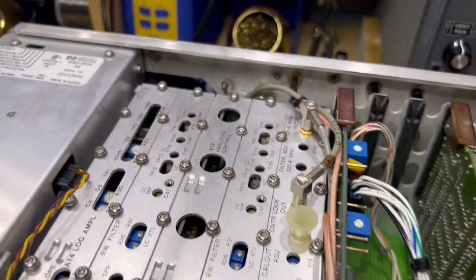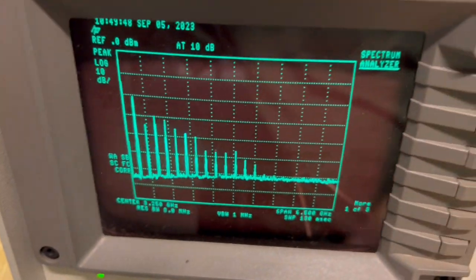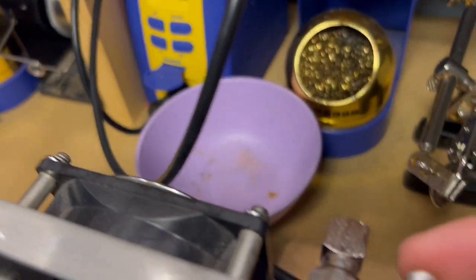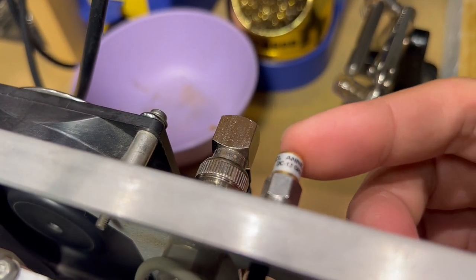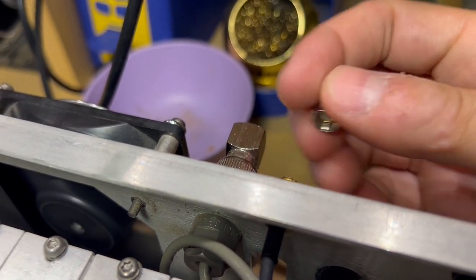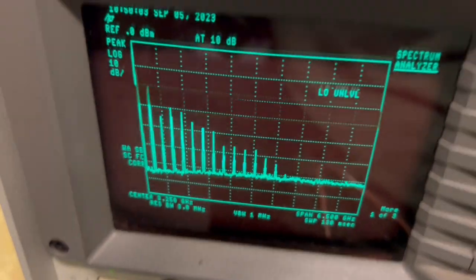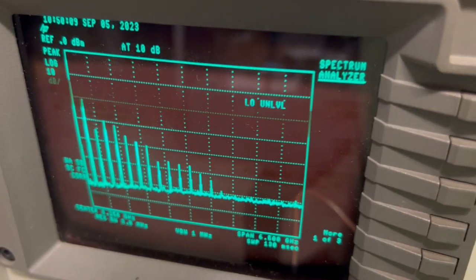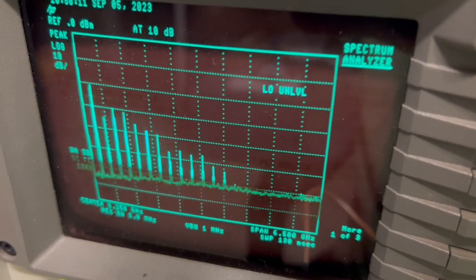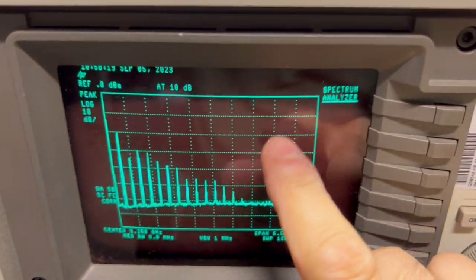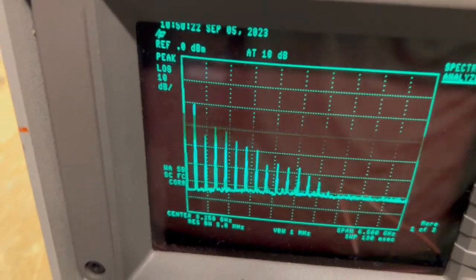Important: on the back panel there's a first LO out connector that requires a 50 ohm terminator. Removing the terminator causes a 'LO unlevel' error on the display. Putting the terminator back on clears the error. Make sure that LO out signal is properly terminated when you have this option installed.